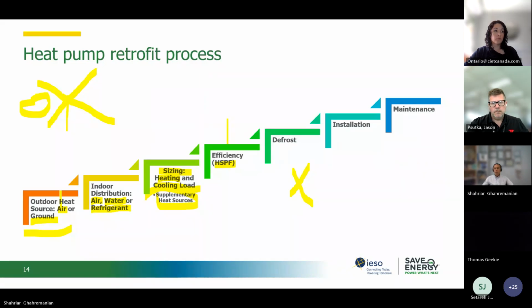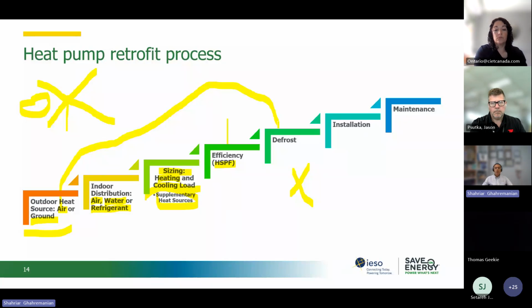If you select an air source heat pump, which means that the outdoor unit is going to be sitting outside, then defrost becomes an important factor, actually, especially for commercial buildings. I worked on a project for installing heat pumps in Thunder Bay, actually. And the good thing is that, because of avoiding the defrost, avoiding any snow or ice accumulation, and better defrost, actually, helping the heat pump, we decided to install the heat pump inside the mechanical room, which was in the penthouse, actually. And then we had some grills in front of it. So it was a great performance that we saw.